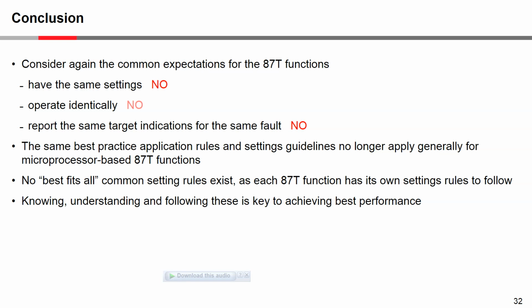Operate identically. Well, I made this a lighter color, and the only reason why I really bring this one up is because when I say operate identically, we know that if you select the Y side as the phase reference, you do have slightly better sensitivity because the calculated differential current is a bit higher. So essentially, the expectation is that the relay would operate for the fault, but you could have slightly better sensitivity when you select the Y side as the phase reference.